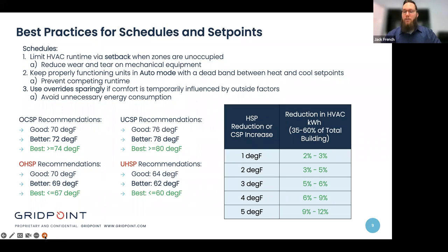space. So best practice would be to go to 80 degrees or potentially above, based on how well your unit's able to recover and maybe things like your climate zone. These are going to be best practice recommendations for units that are able to respond properly and condition spaces effectively and consistently. And then, talking about how changing your set points can influence your overall energy consumption.